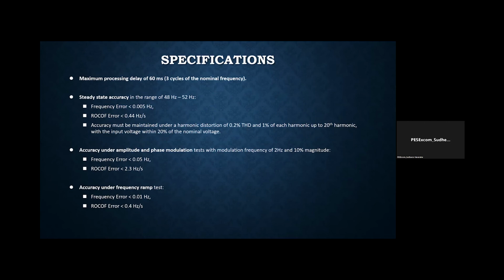As Dr. Anton explained, these measurements are taken using current transformers and voltage transformers, which step down the voltages and currents before inputting them into the PMU - that's how the voltage reduction works.